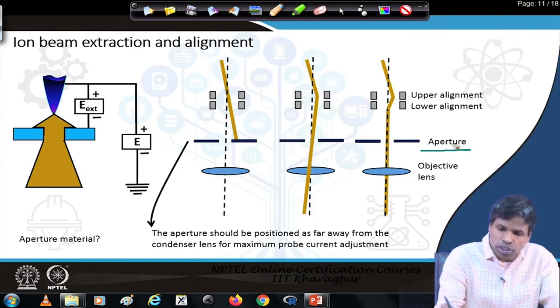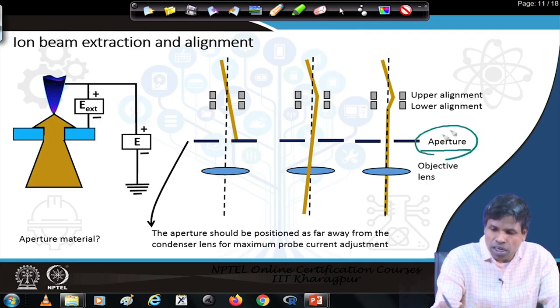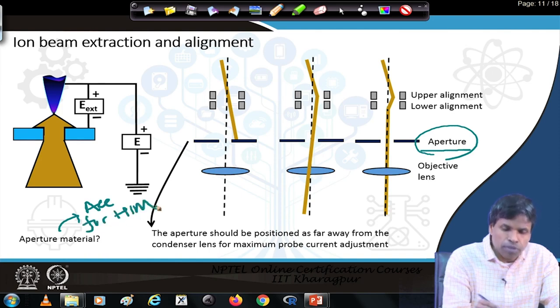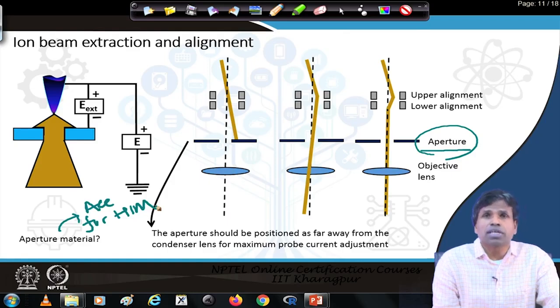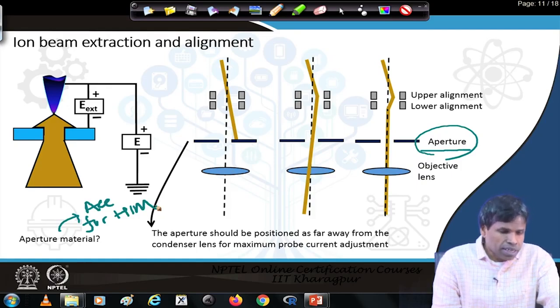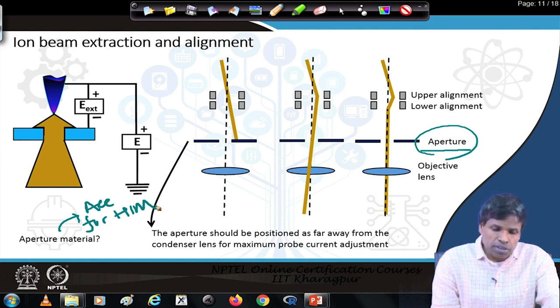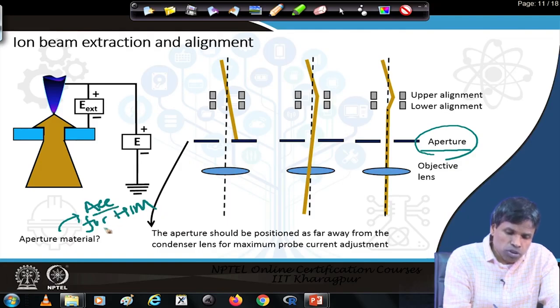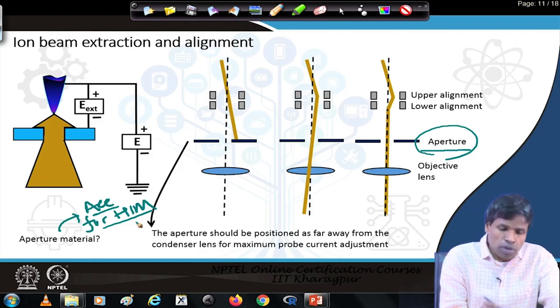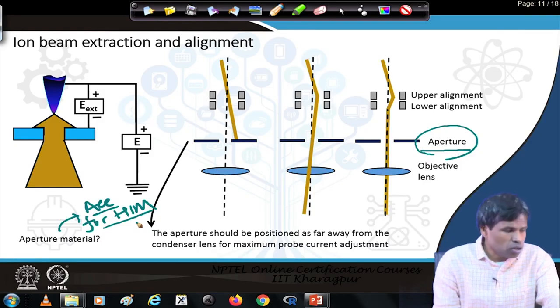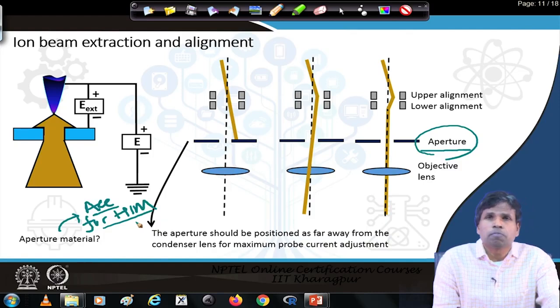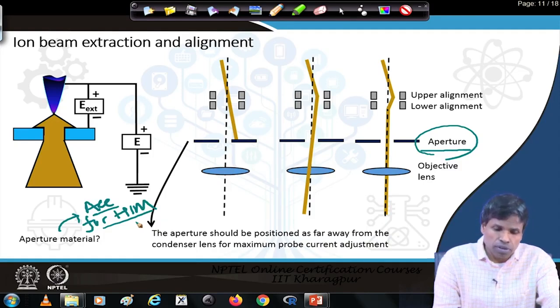Regarding aperture material: for helium ion microscopy, the aperture material is gold (Au), because a gold aperture produces less contamination and also less beam scattering. Gold aperture is used because of reduced beam scattering and less contamination. However, helium ions will keep on bombarding this aperture, slowly sputtering the gold aperture, and from time to time a new aperture should be used for microscopy purposes. Otherwise the aperture diameter will keep increasing and the aperture may become perforated.